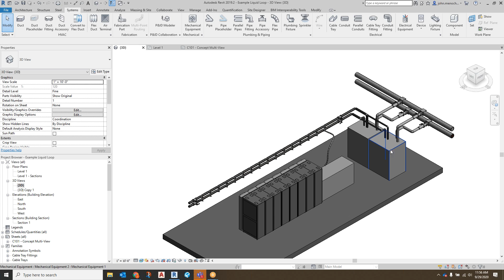As you guys mentioned, ASHRAE 90.1's velocity limit for some of the latest plastic pipe technology is too low, like 7.5 for larger size pipe. I think plastic pipe can carry water at a lot more velocity, maybe 10, 11, 12. That's probably worth looking at, because the newer plastic pipes can carry higher velocity water.